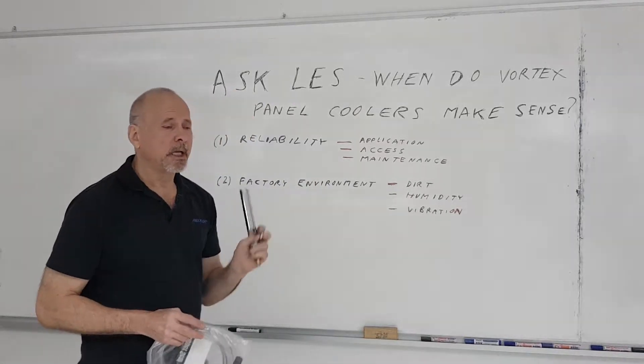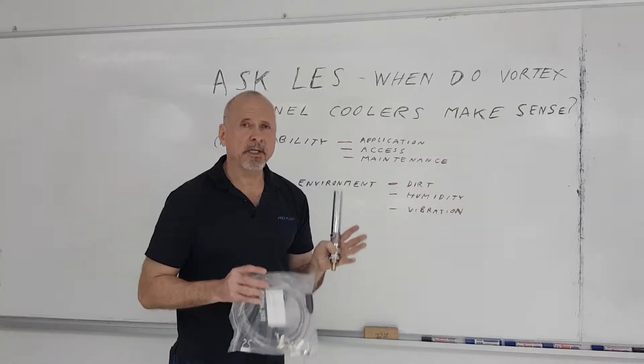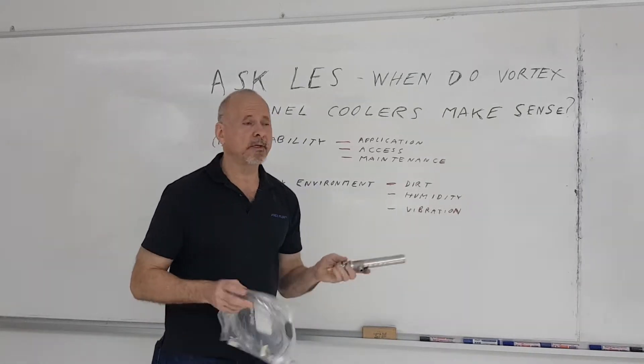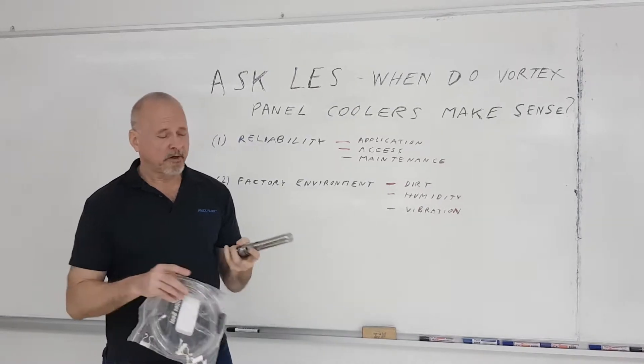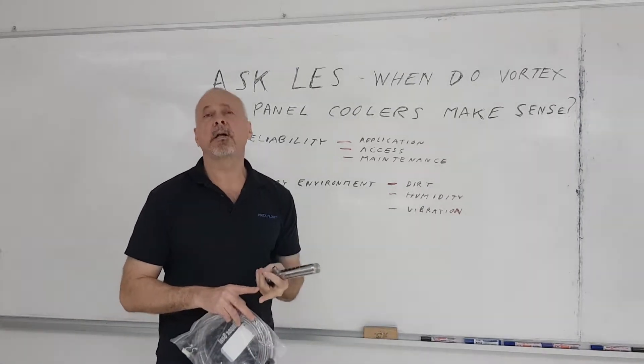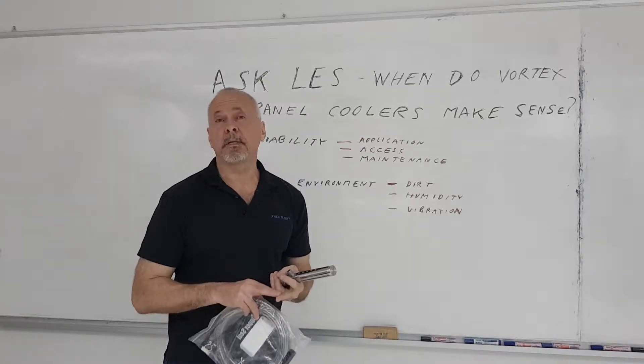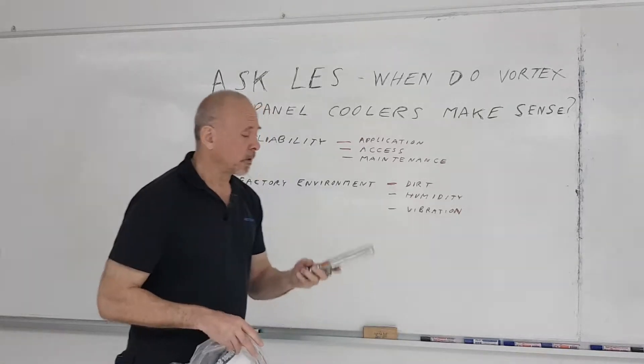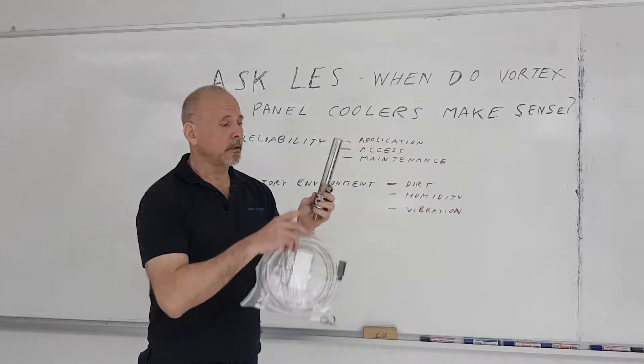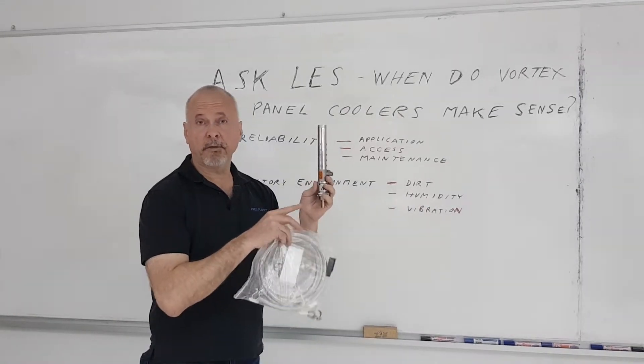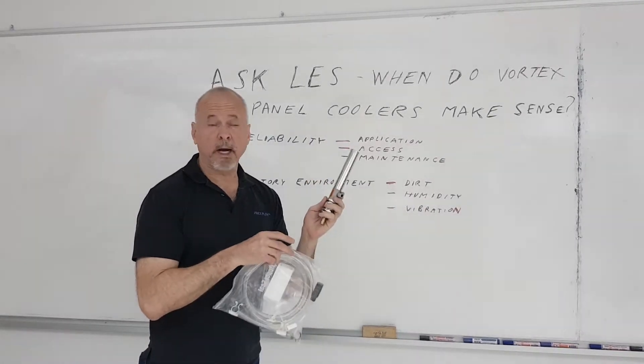Secondly, consider how often the air conditioner actually has to be operating. For example, variable frequency drives get hot on startup, but after that they cool down and don't need the air conditioning effect. So a panel cooler can simply be hooked up through a solenoid valve and a thermostat, and it will go on when required and go off when required.